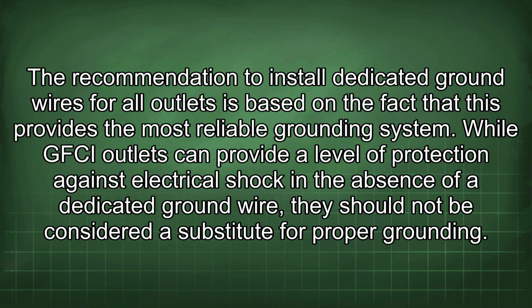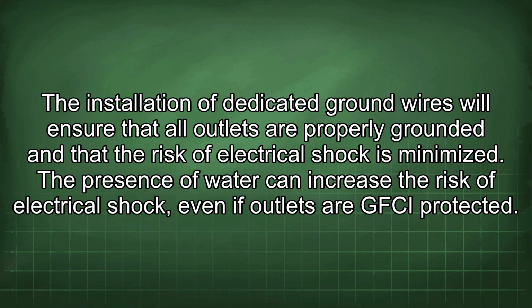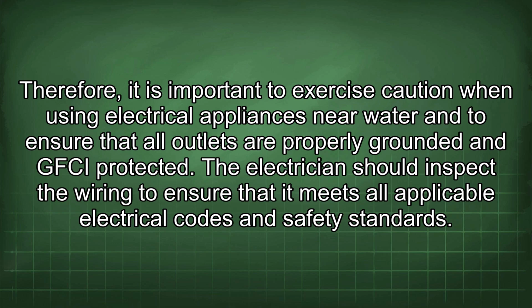The recommendation to install dedicated ground wires for all outlets is based on the fact that this provides the most reliable grounding system. While GFCI outlets can provide a level of protection against electrical shock in the absence of a dedicated ground wire, they should not be considered a substitute for proper grounding. The installation of dedicated ground wires will ensure that all outlets are properly grounded and that the risk of electrical shock is minimized. The presence of water can increase the risk of electrical shock, even if outlets are GFCI protected. Therefore, it is important to exercise caution when using electrical appliances near water and to ensure that all outlets are properly grounded and GFCI protected.